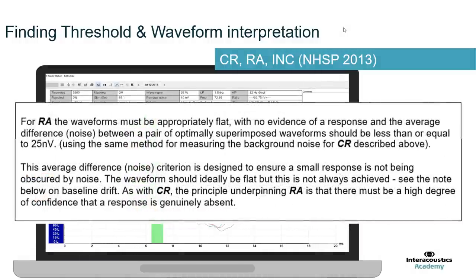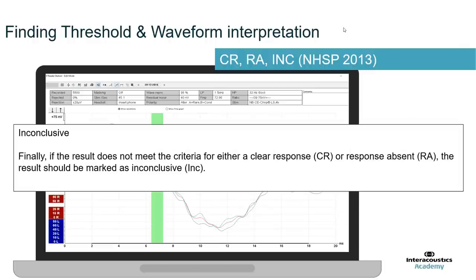If we don't have a clear response: if the quality is good — meaning residual noise is low — and there is no form of ABR, seeing essentially a flat line on screen, then we can call it response absent, using the value of 25 nanovolts in their description. If the waveform isn't a clear response or response absent, it should be marked as inconclusive. To turn an inconclusive waveform into a clear response, simply continue averaging or run another trace and merge the curves to improve the residual noise calculation.